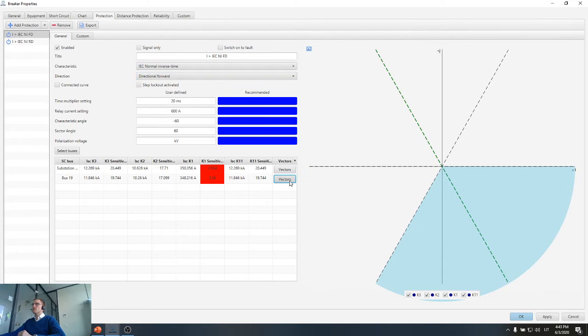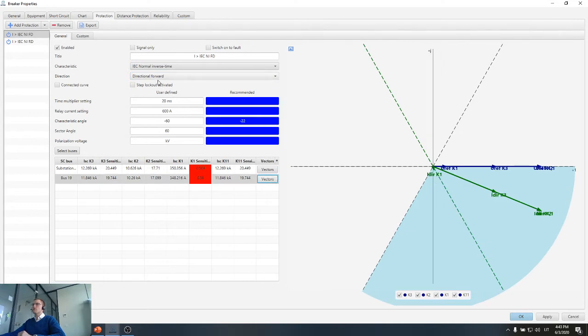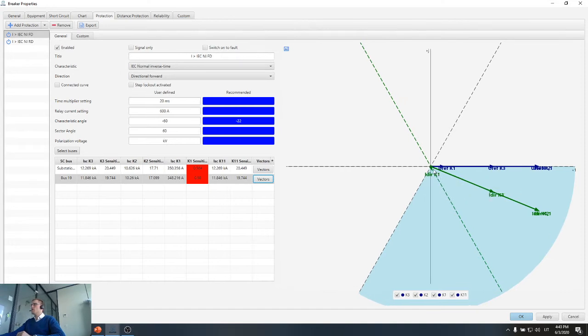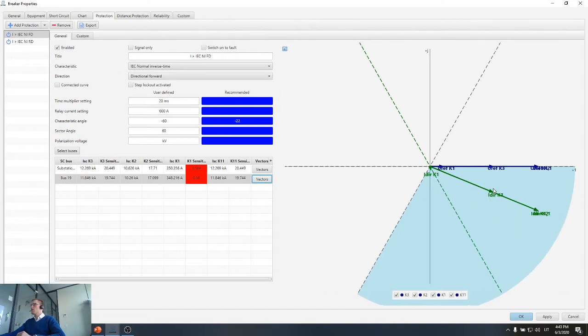So in case of forward direction protection device, we can see that all the short circuit currents are looking like that. So these are vectors of short circuit currents, and they are inside the blue area, which represents the directional protection device operation zone. So the user actually has to select this zone manually. He gets, of course, recommendations how to do that in order to set directional protection devices.